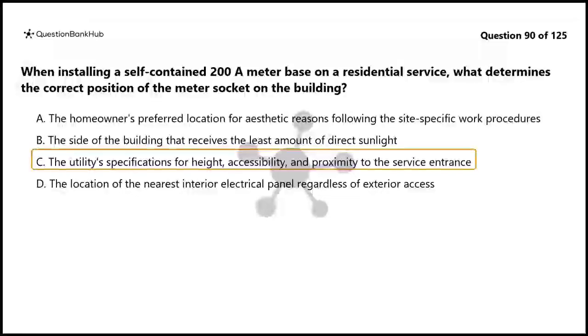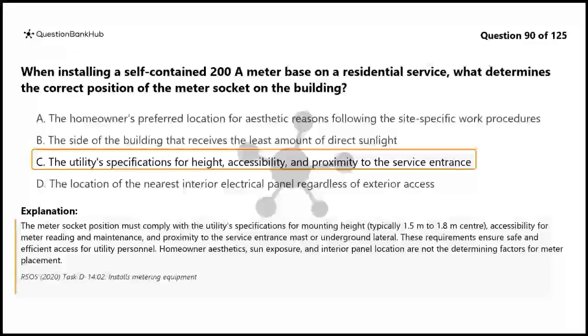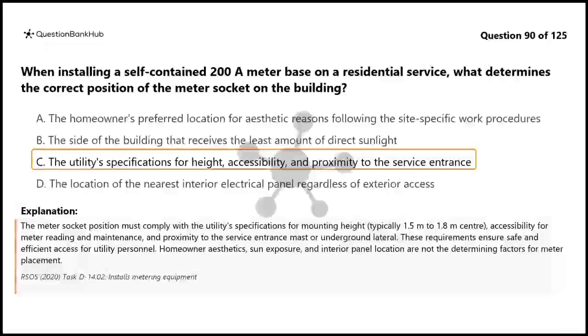The correct answer is C. The meter socket position must comply with the utility specifications for mounting height, typically 1.5 meters to 1.8 meters center, accessibility for meter reading and maintenance, and proximity to the service entrance mast or underground lateral. These requirements ensure safe and efficient access for utility personnel. Homeowner aesthetics, sun exposure, and interior panel location are not the determining factors for meter placement.